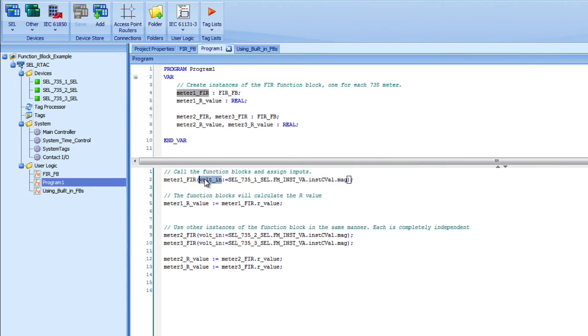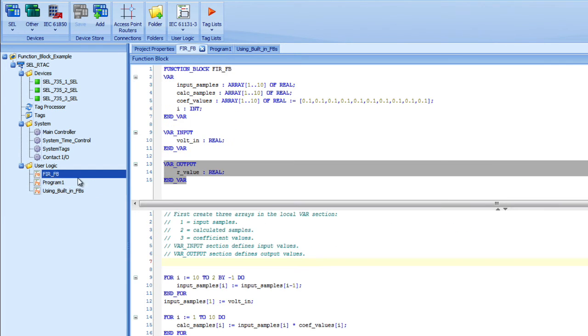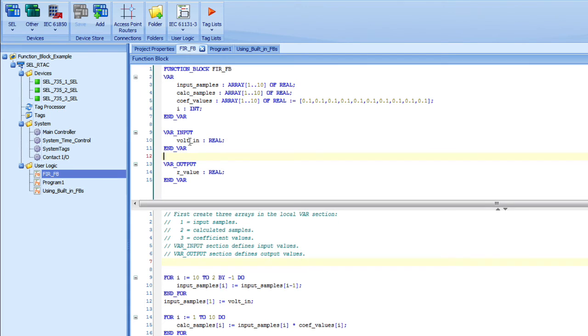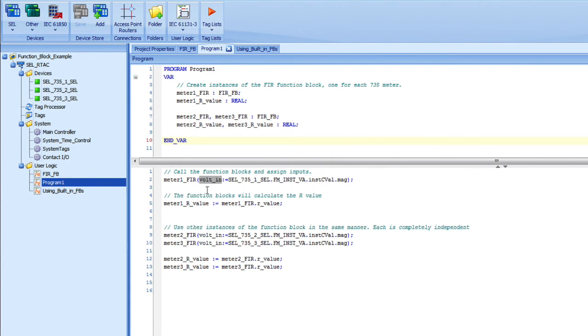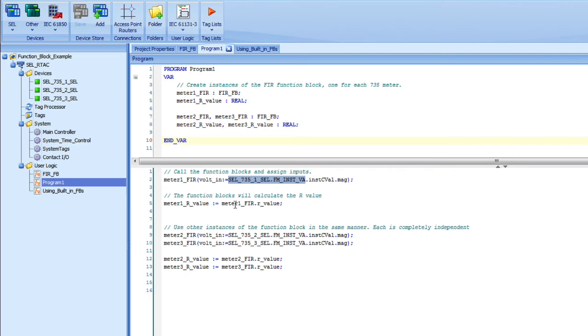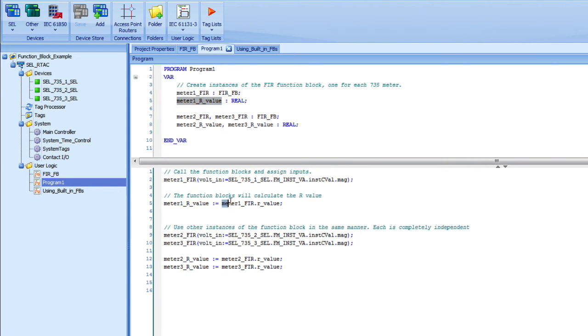Then I assign any inputs. I only have one input in this example, but I could have multiple ones. This one's called VoltIn. I'm going to go back to my function block and you can see that my var input is VoltIn. I assign it to a value. In this case, the value is a voltage that I'm getting from a 735 meter. To receive the output, I have a variable called meter1_R_value. It's a local variable that I created. I assign the value of meter1_FIR.R_value to meter1_R_value.